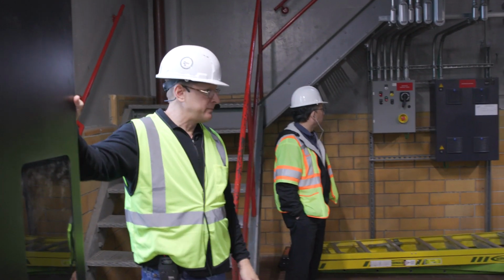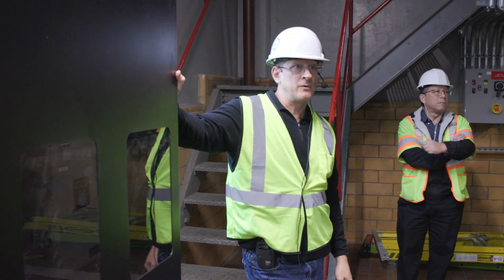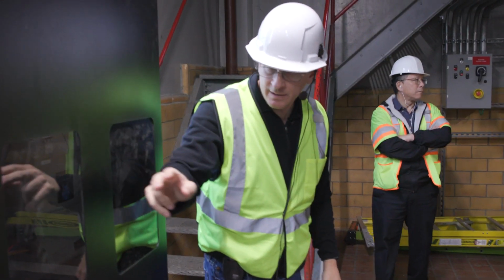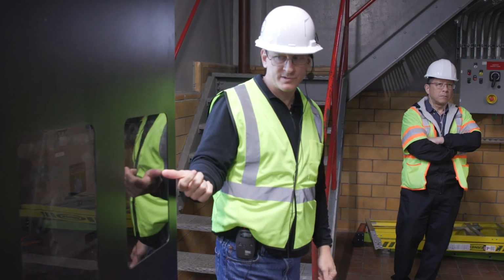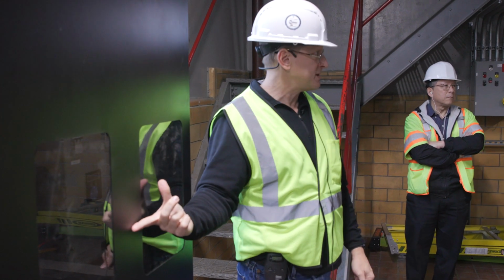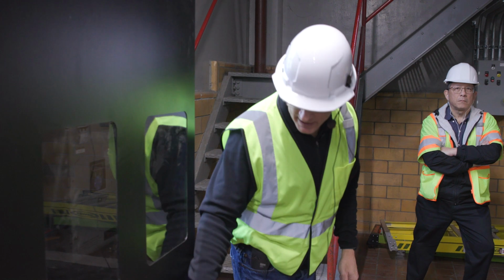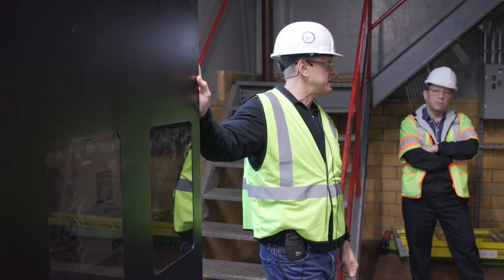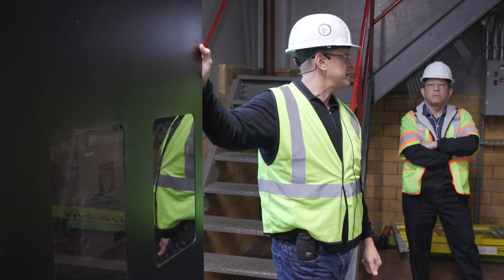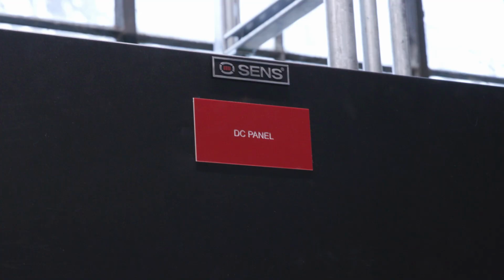So this is our DC panel. Again, it's fed from the ADP for one feed for one of its rectifiers, and then from our UCP for the other rectifier. So there's two rectifiers for charging the station batteries in this panel, and then you've got the batteries down below, basically providing your 125 volt DC control voltage for your batteries and the medium voltage switchgear. There's a 125 volt DC panel on the side for your individual feeds for various controls into the switchgear. So not only do we feed control voltage for the breakers, but we also feed the heating elements in the switchgear itself, or the panel heaters in the switchgear.